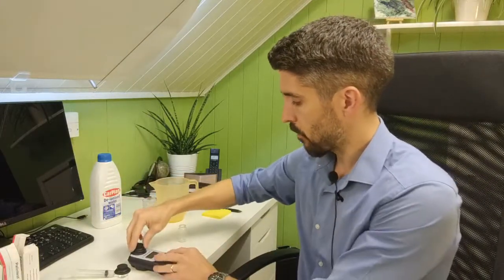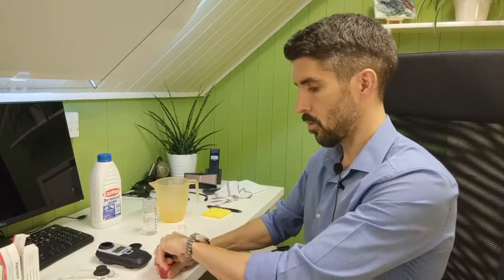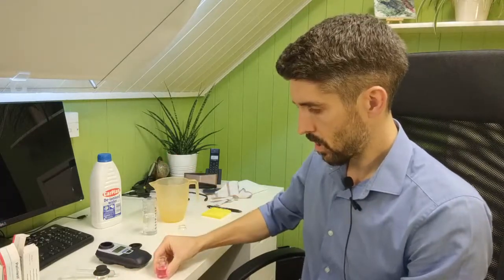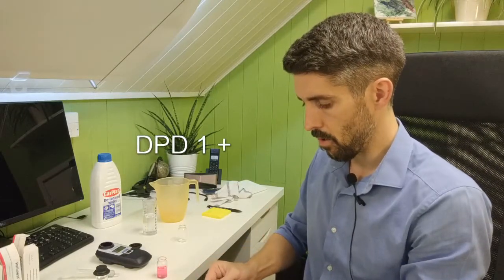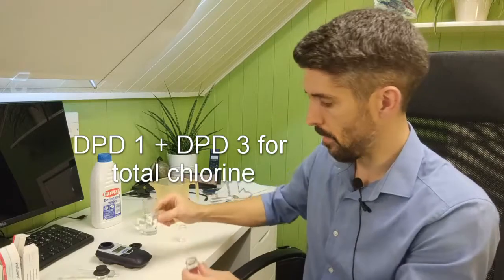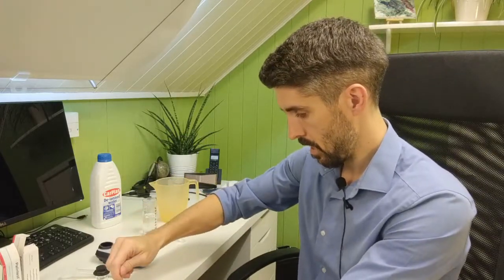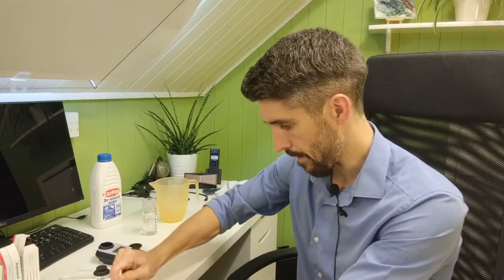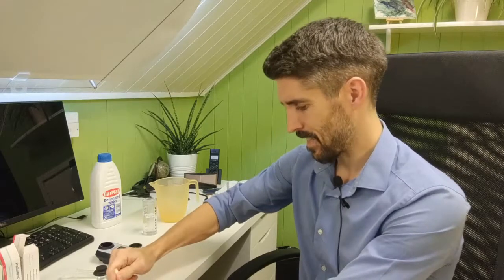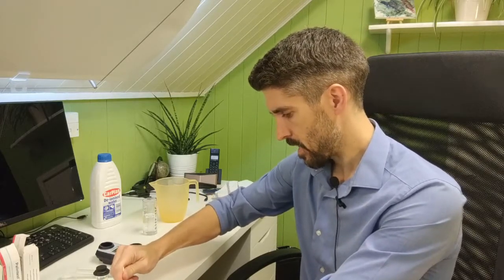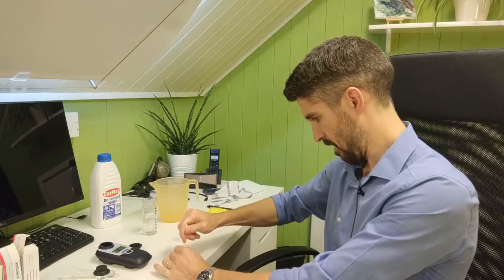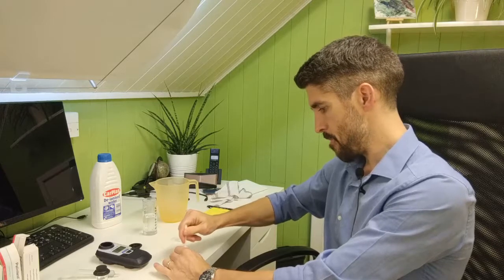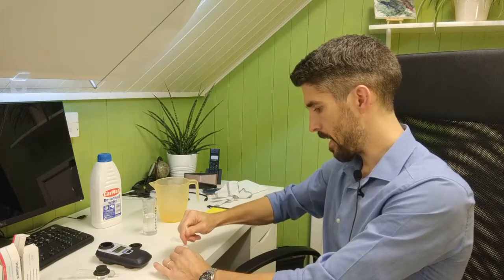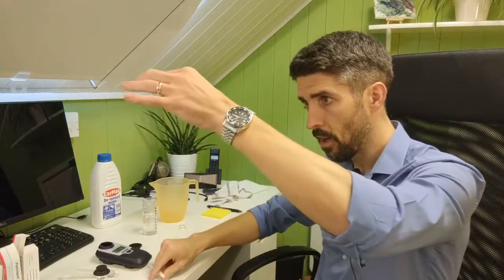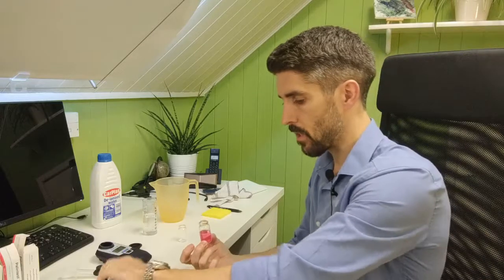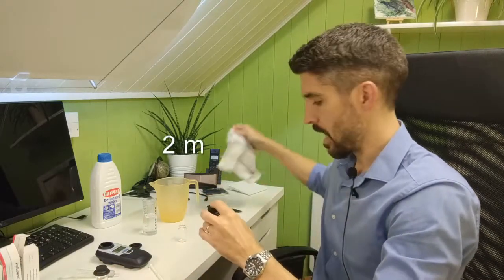What we want to do now is a test for total chlorine. So what you do is, to the same sample that you added the DPD1 tablet to, add a DPD3 tablet to it, and then crush it up again in the same way as you did with the DPD1. But what you'll find is that the DPD3 usually takes a little bit more effort to crush up. Again, make sure that you've completely dissolved the tablet and then leave it for 2 minutes. It's a 2 minute reaction time for the DPD3.